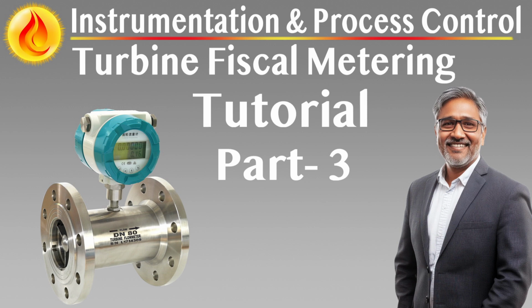and temperature range. The preferred installation position is downstream of the turbine meter to reduce upstream disturbances and preserve meter accuracy. Actuators must be sized with sufficient margin to overcome differential pressure and ensure positive sealing. Properly selected and configured flow control valves enable flexible, safe, and stable operation of the metering system, especially when adjusting for process fluctuations or initiating calibration cycles. Their performance directly influences measurement repeatability, prover compatibility, and system responsiveness.